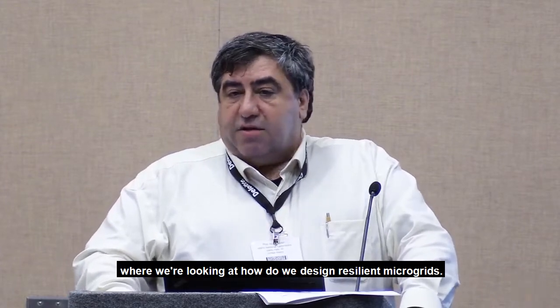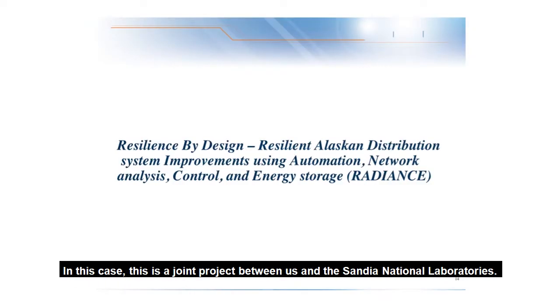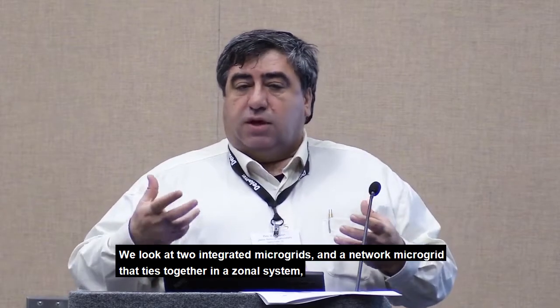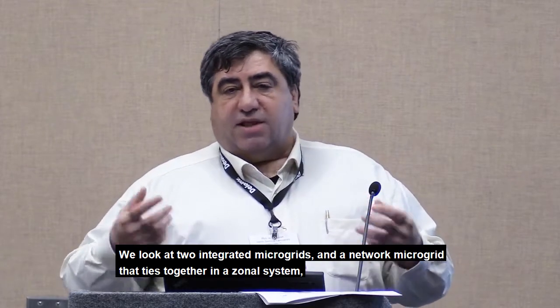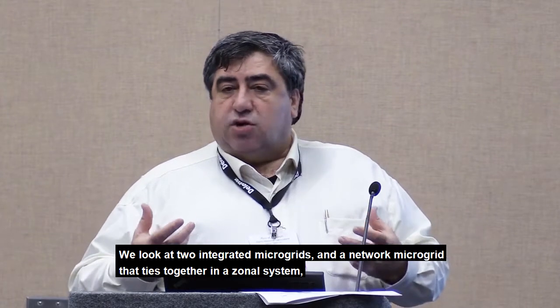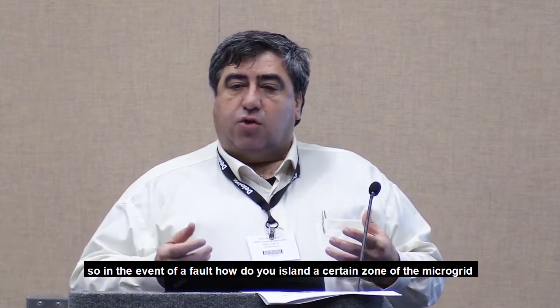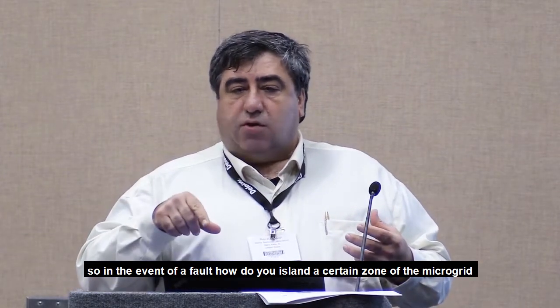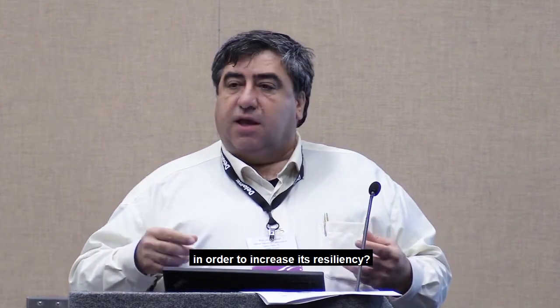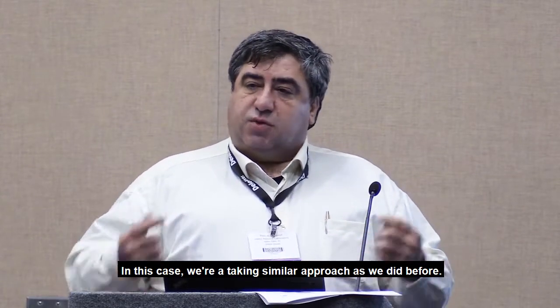This is part of the grid modernization activity for the Department of Energy, where we're looking at how to design a resilience microgrid. In this case, it's a joint project between us and Idaho National Laboratory, where we look at two integrated microgrids, a network microgrid that ties together in a zonal system. So in the event of a fault, how do you island certain zones of the microgrid in order to increase its resiliency? In this case, we're taking a similar approach as we did before.